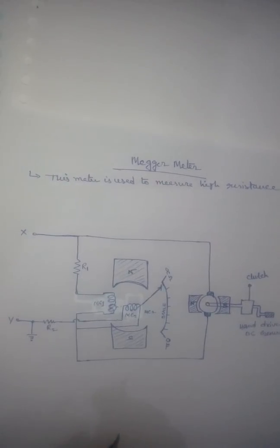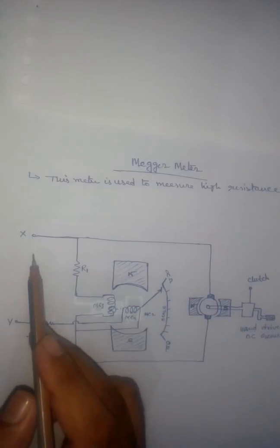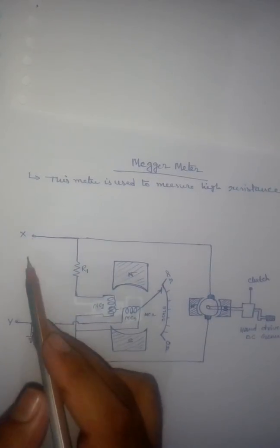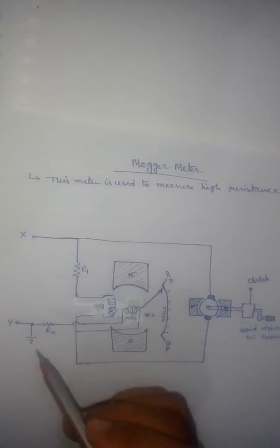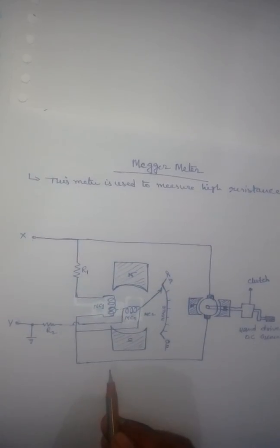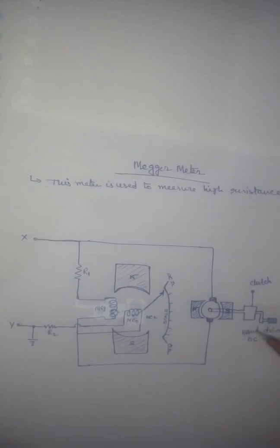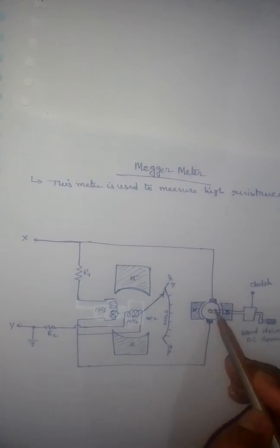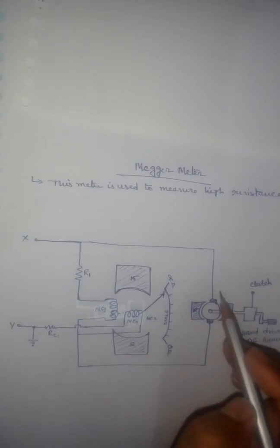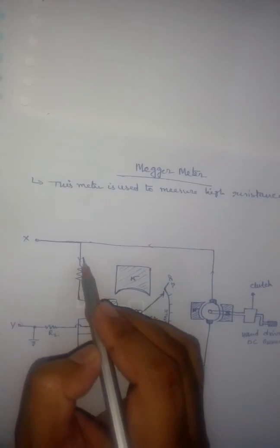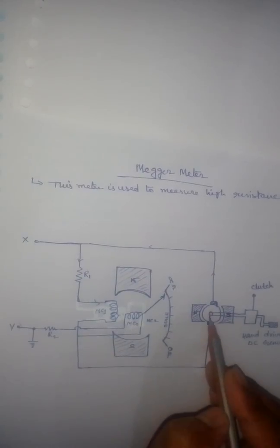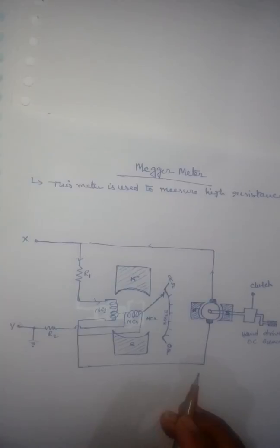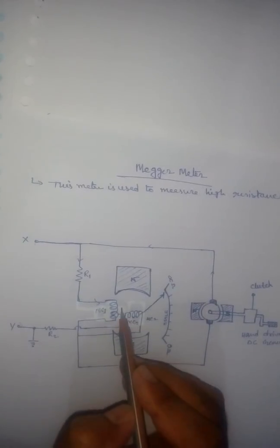Now we will see the working of the Megger. First, suppose no object, no insulator, and no test element is connected — that means the X-Y terminals are open. When we drive the hand-driven DC generator, it will generate some DC voltage and current, and that current will flow only through MC1, the moving coil 1.